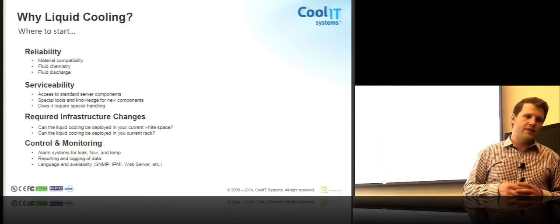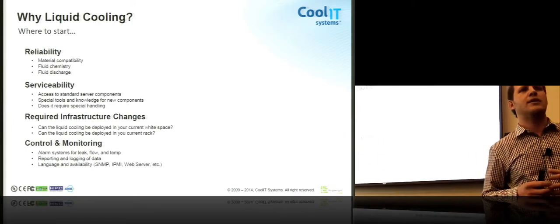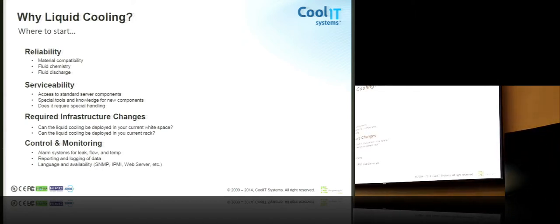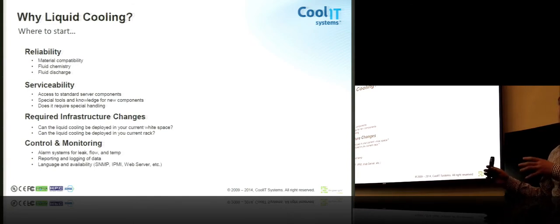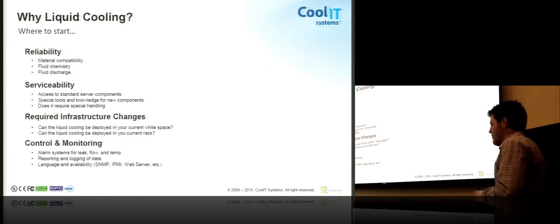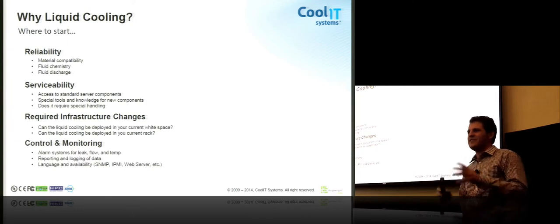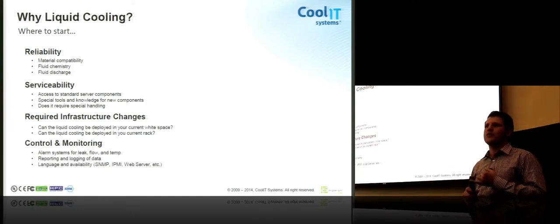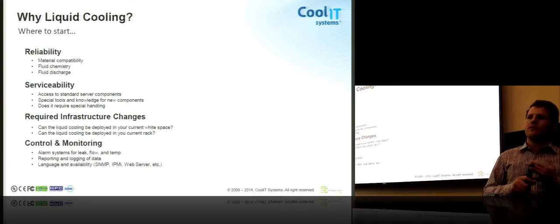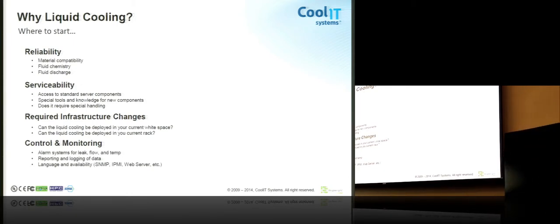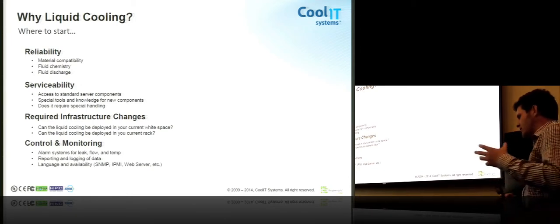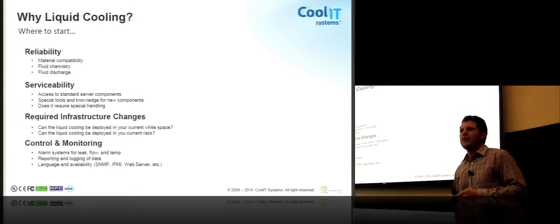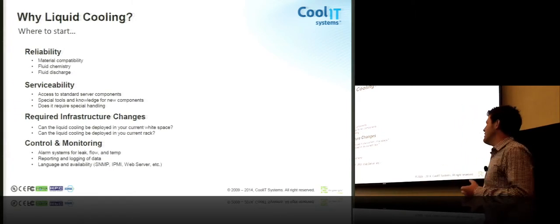So, if I look at the design theory of the Rack DCLC product for CoolIT, when we were thinking of the product and adapting it from the desktop to the data center market, we really thought to ourselves, could the same person that works on the IT day in, day out, work on the liquid cooling system? So, when we ship our systems outside of the CHX 650, but the CHX 40, it ships filled and charged with coolant. Our manifolds ship filled and charged with coolant. Our server modules ship filled and charged with coolant. So, everything is more or less plug and play.